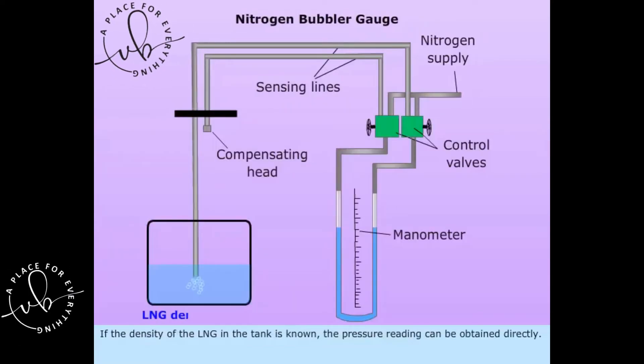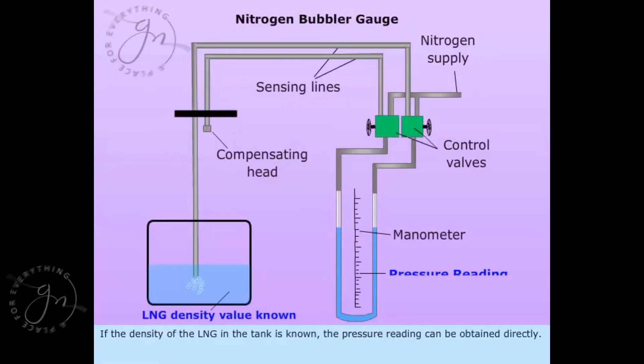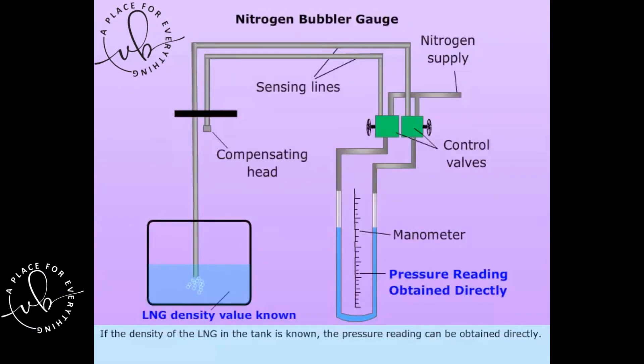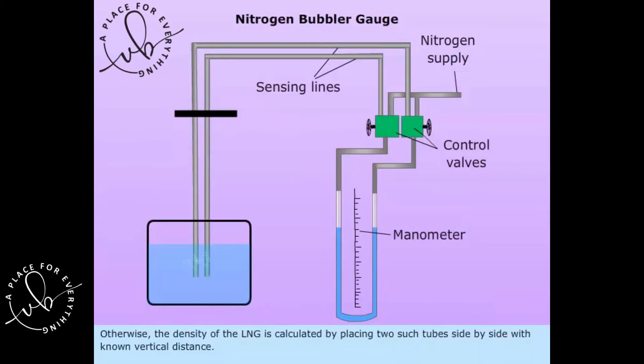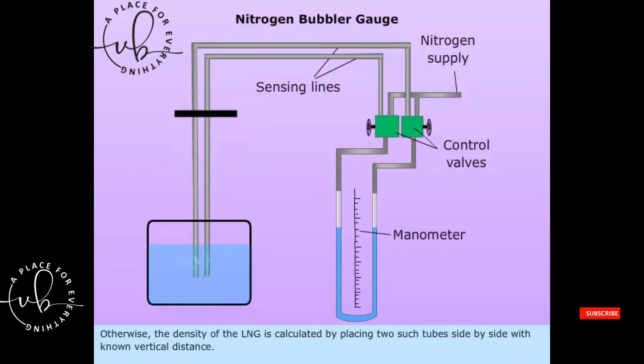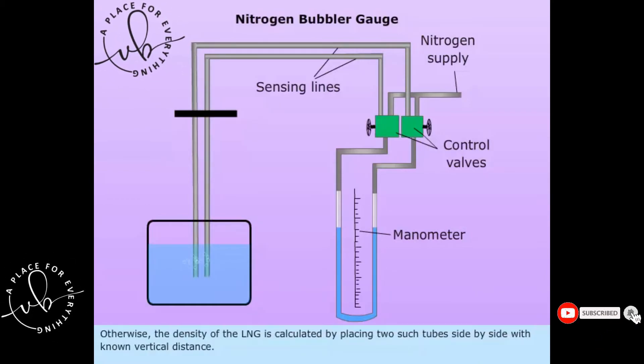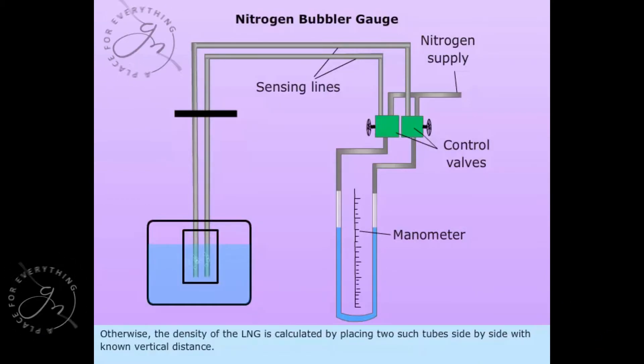If the density of the LNG in the tank is known, the pressure reading can be obtained directly. Otherwise, the density of the LNG is calculated by placing two such tubes side by side with known vertical distance.